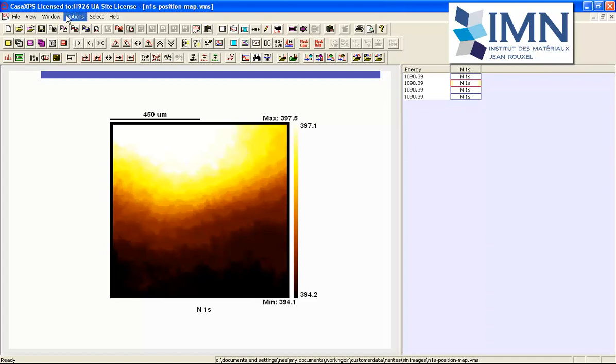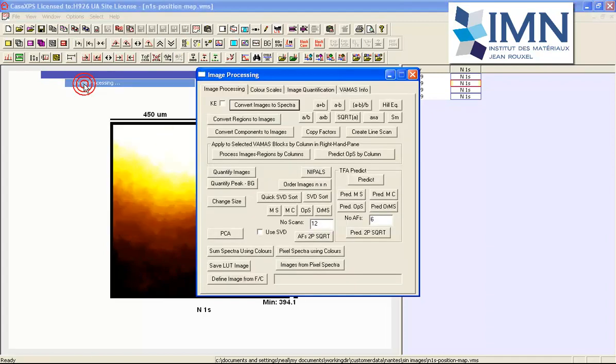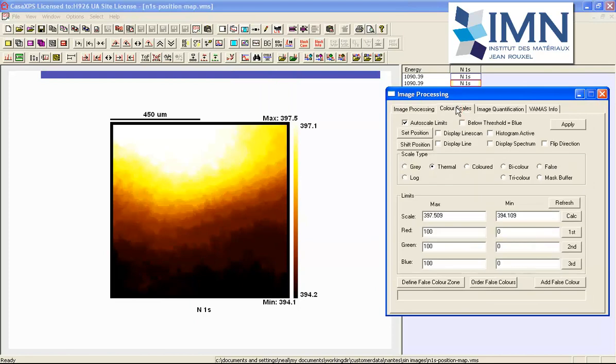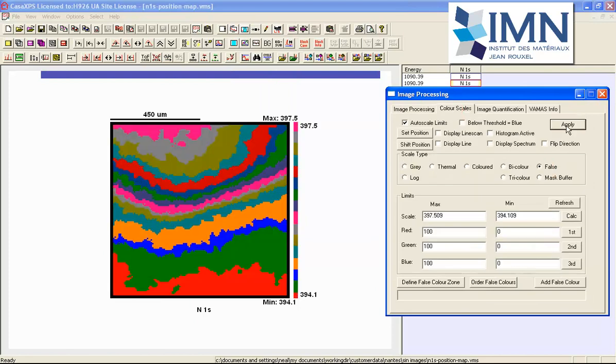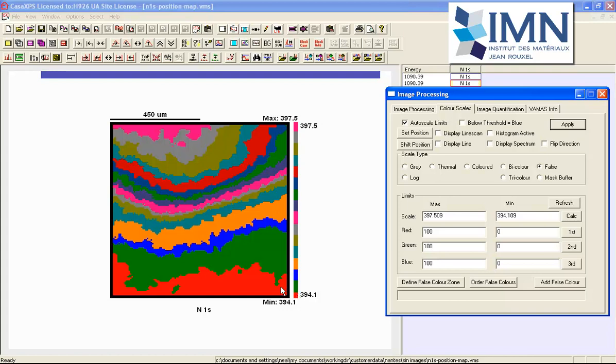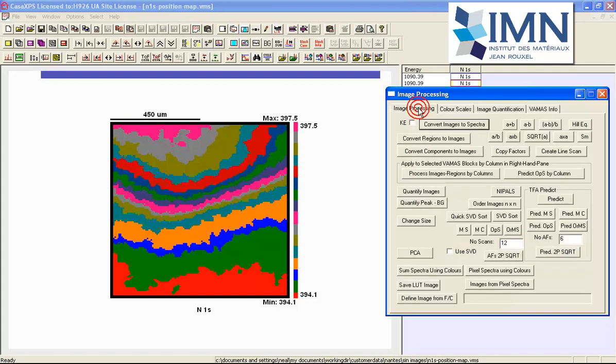We can do this by looking at the image processing, the color scale. If we select the false color, I've previously set up a range of false colors for these images so that at each different binding energy a pixel color corresponds. When we sum all the pixels with the common color and form spectra from these common colors, we should end up with spectra that make sense in terms of different nitrogen 1s peaks with binding energies that are shifted as a result of differential charging.